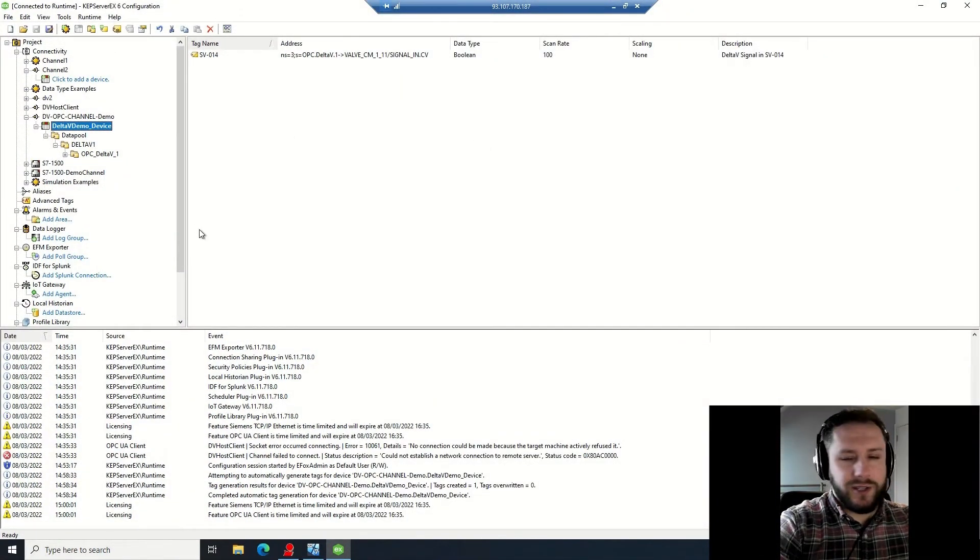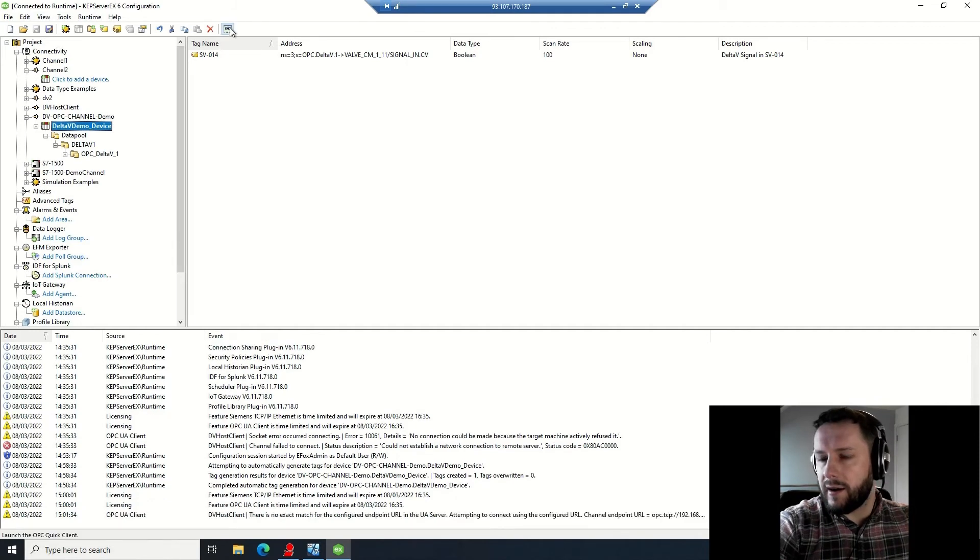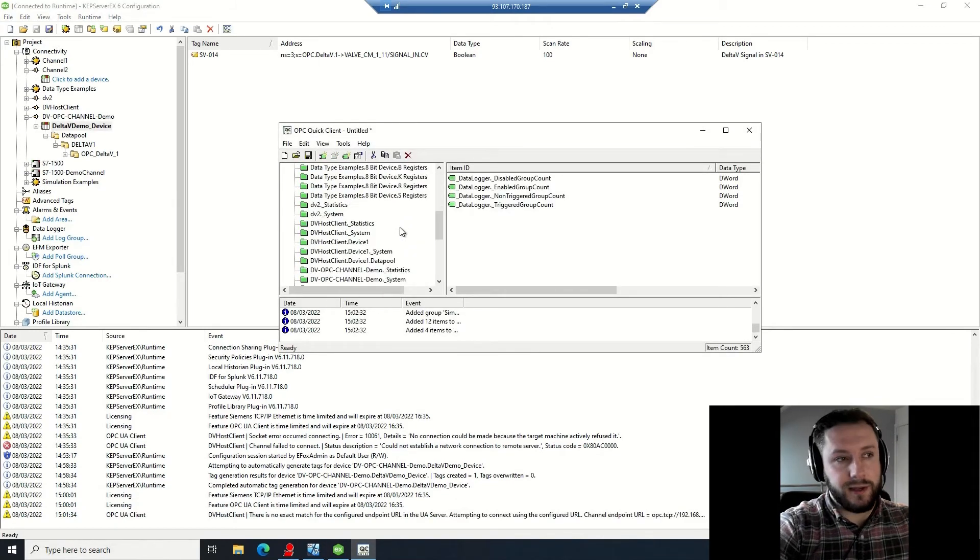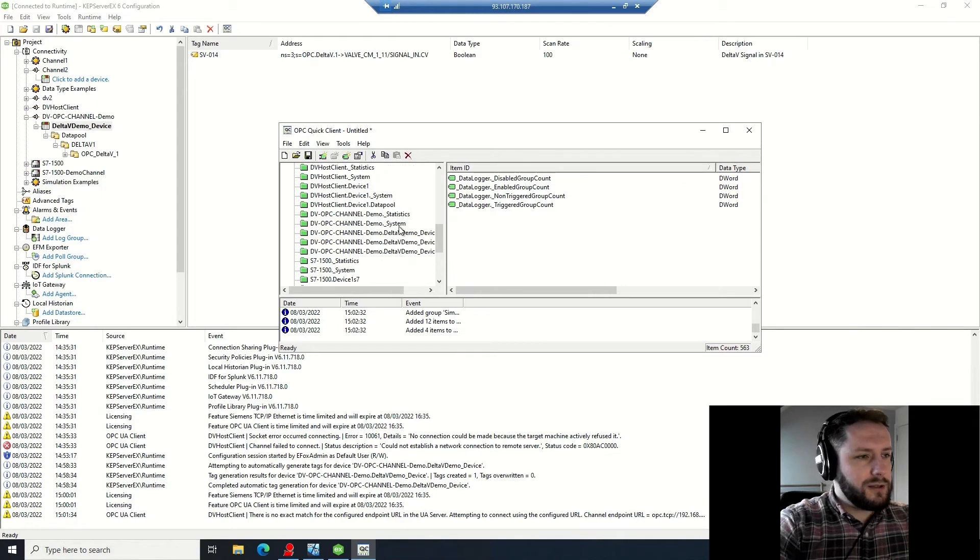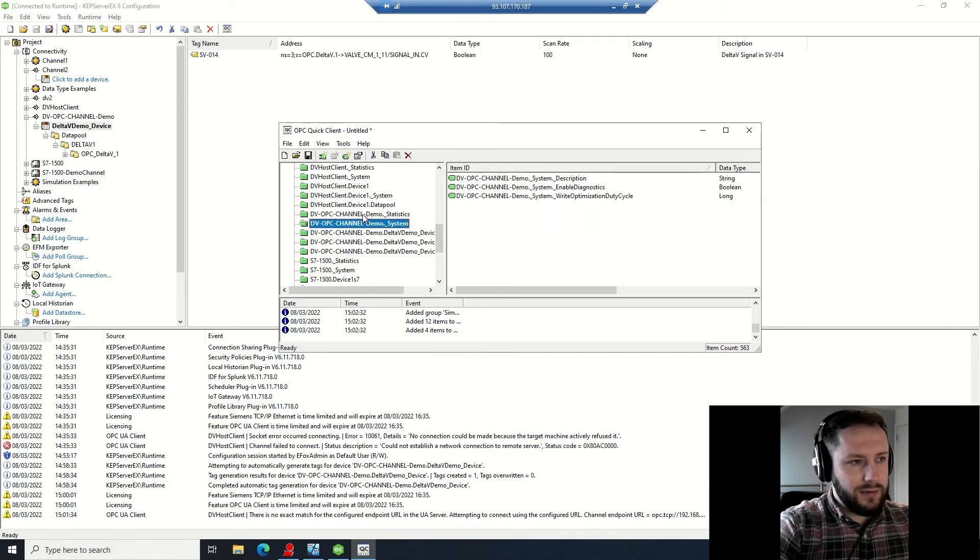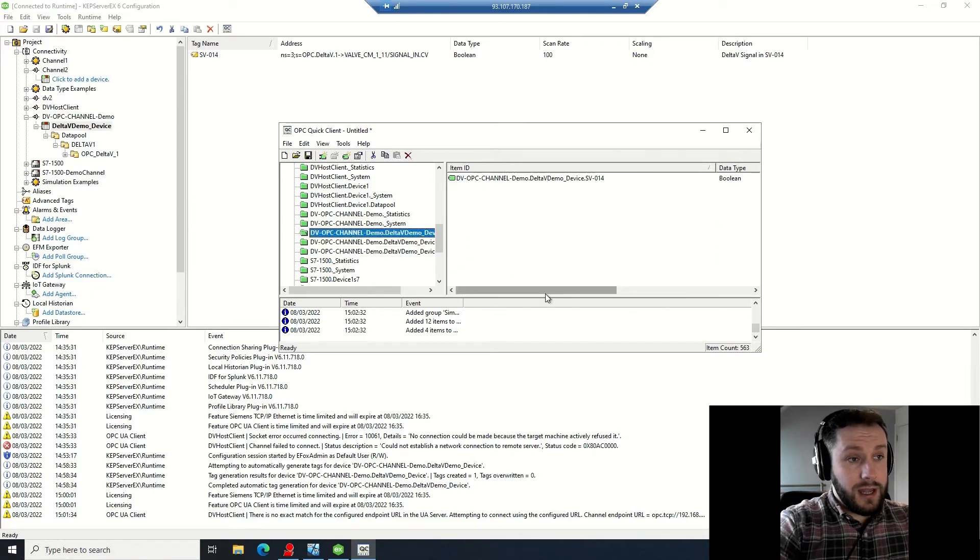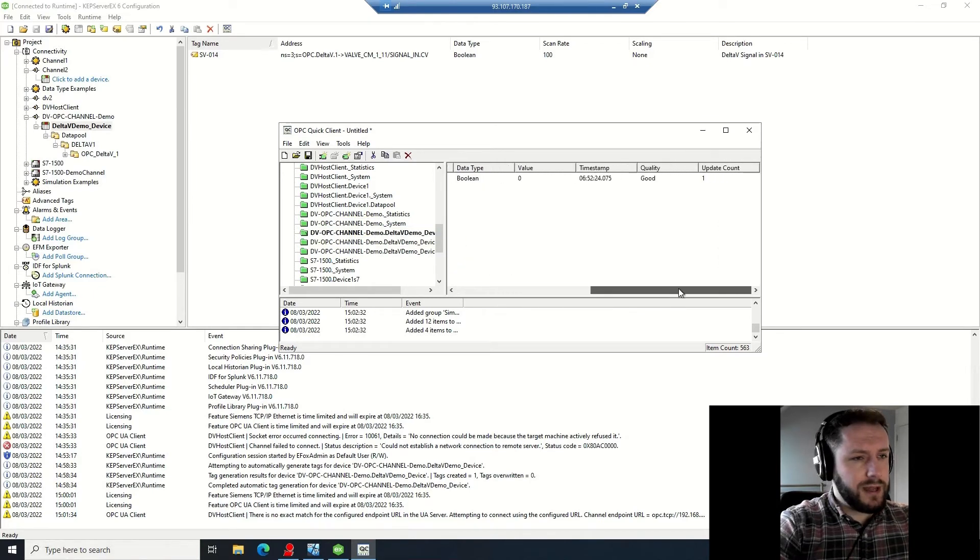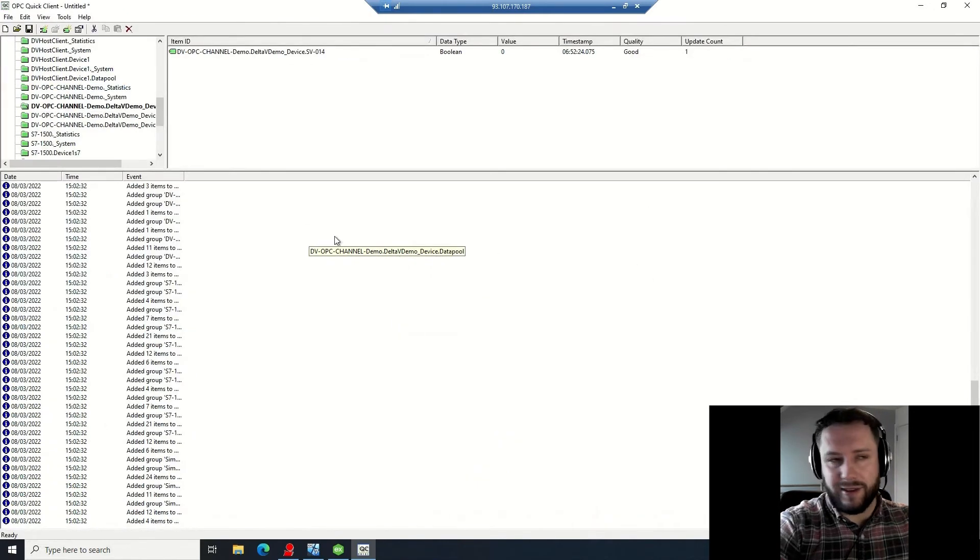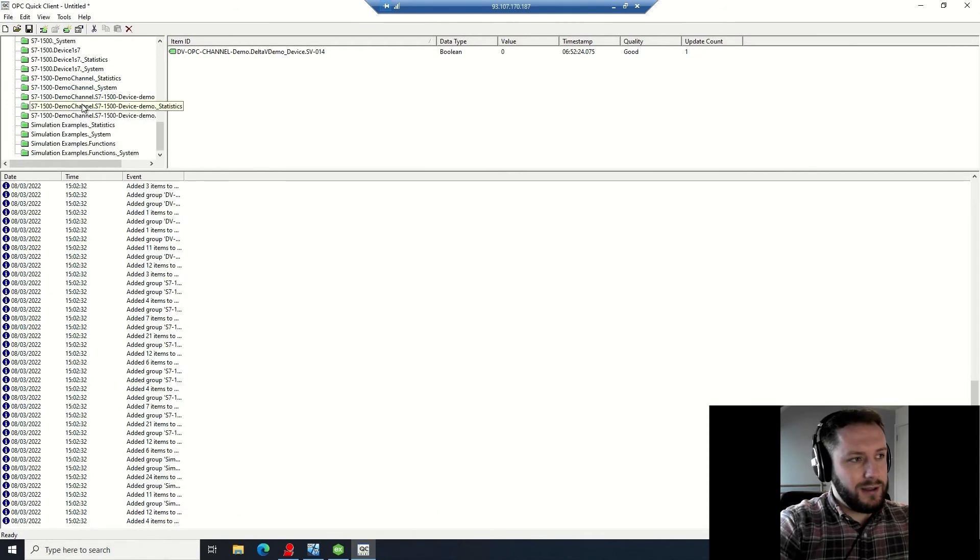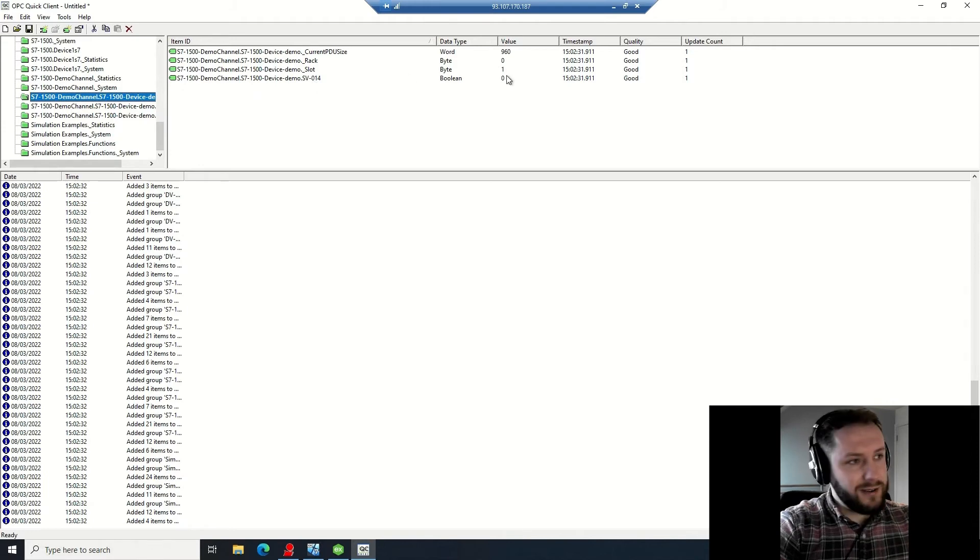And now I'm going to ensure that they are online and communicating correctly by using the OPC Quick Client. So we've created these channels, I'm going to browse these channels, and I'm going to have a look for my tags which I've created, which will be named SV014 in both cases. So quality good - that is your main indicator you're on the right track, and you'll see value there: zero. You will get bad if you've set it up wrong to this point.